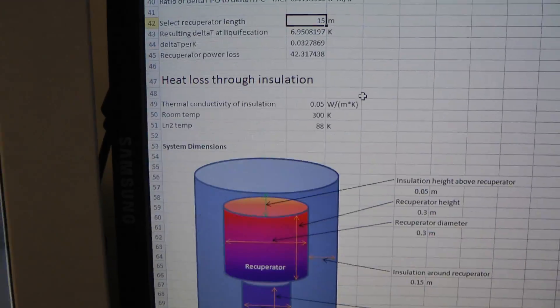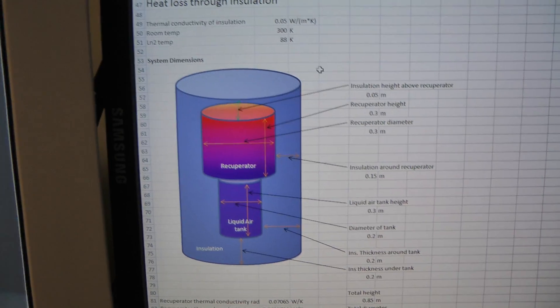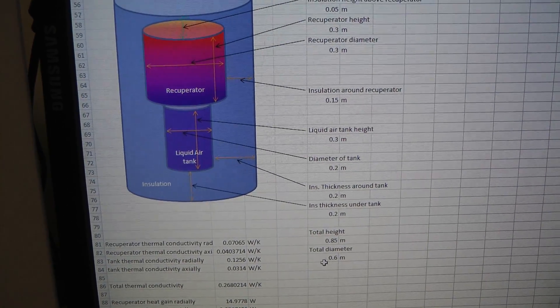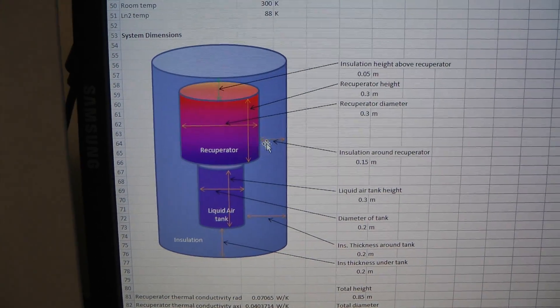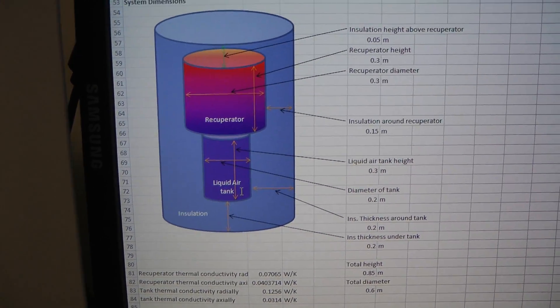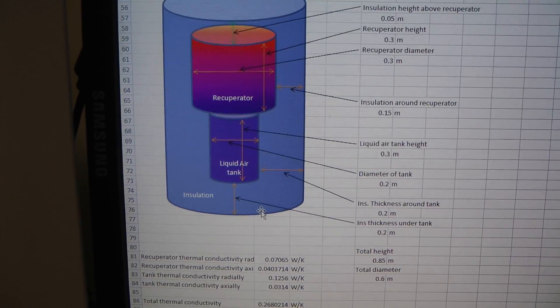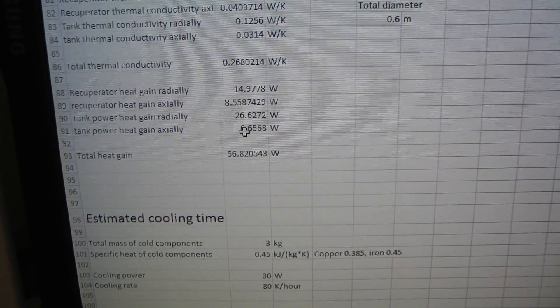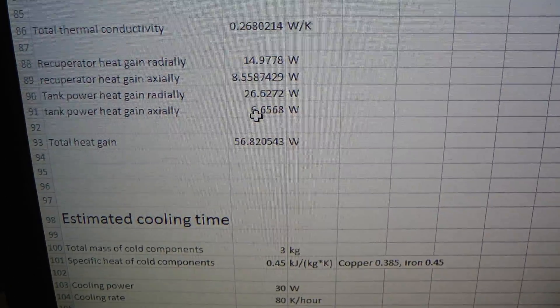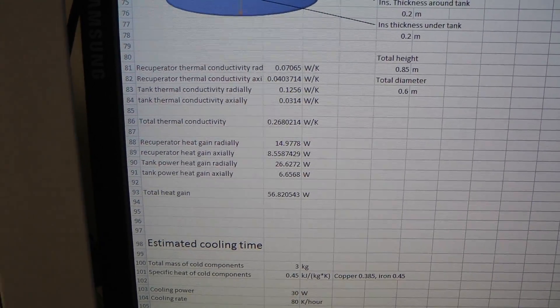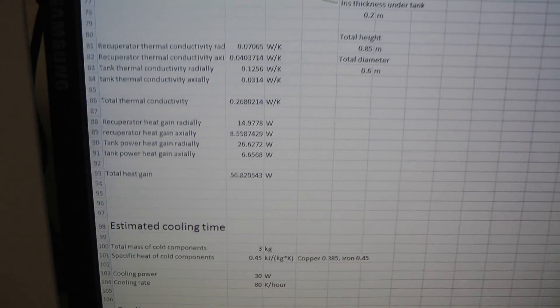I've also looked at the heat loss through the insulation. I just picked some values for the sizes, the thicknesses of insulation, diameters of components, and made some assumptions about the heat flow. We end up getting about 55-56 watts loss through all the insulation, assuming the calculations are right. These are probably a little bit optimistic, but it's not too far off.